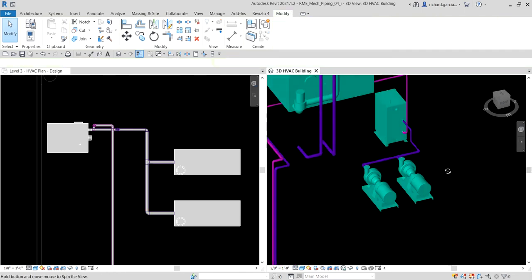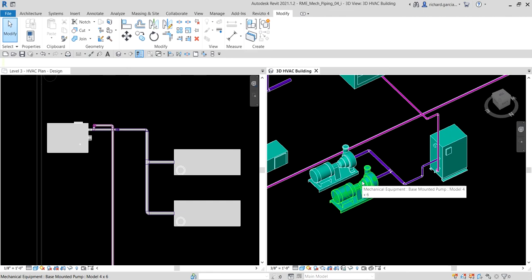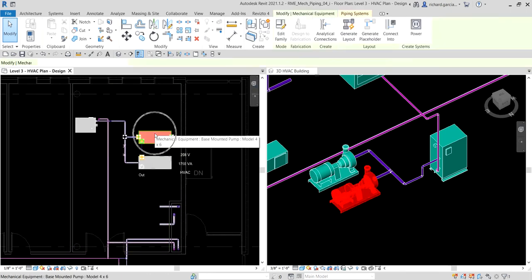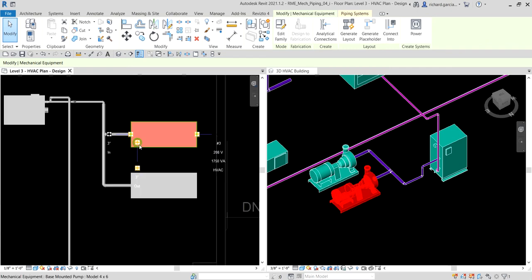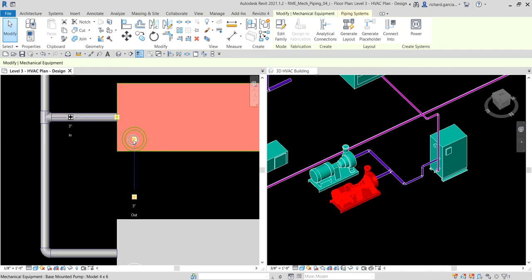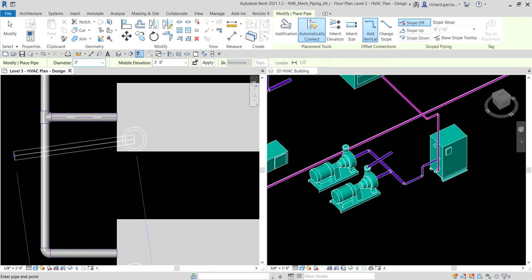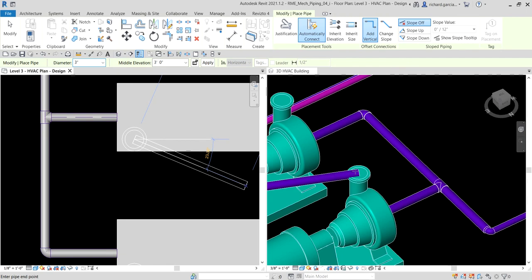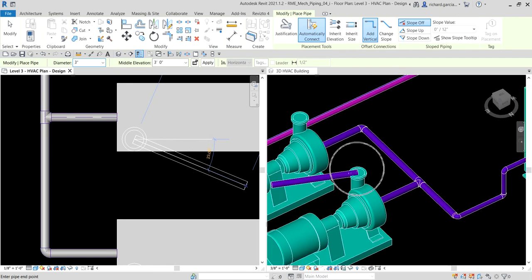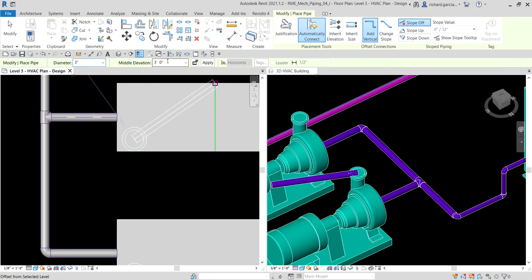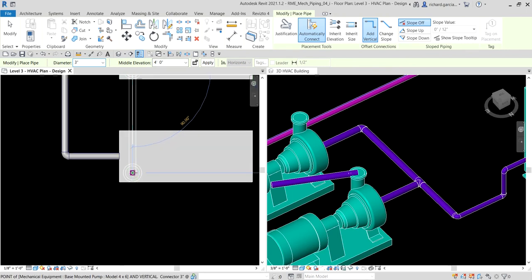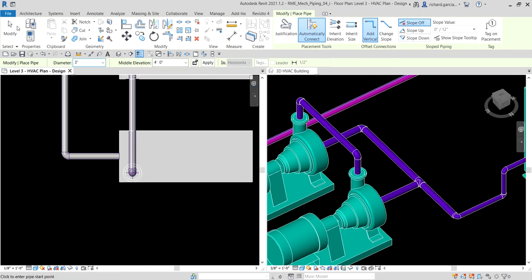Now let's connect the base mounted pumps in parallel. In the plan view, I select the primary base mounted pump, right-click the discharge connector, and select Draw Pipe. Before clicking the destination, I need to adjust the pipe offset — I change the middle elevation to 4 feet and press Enter. Then I click the connection point.